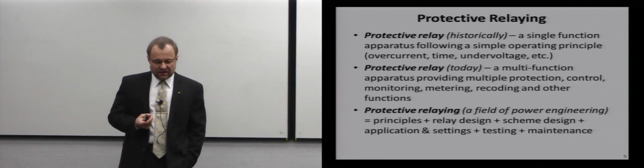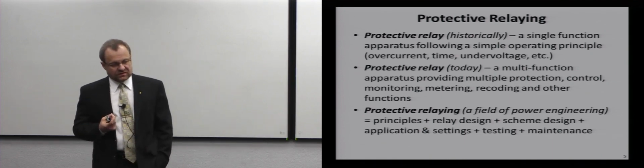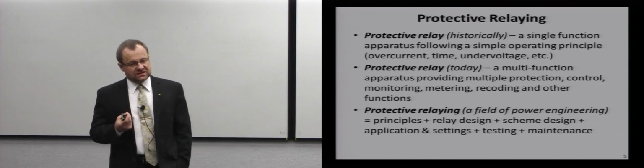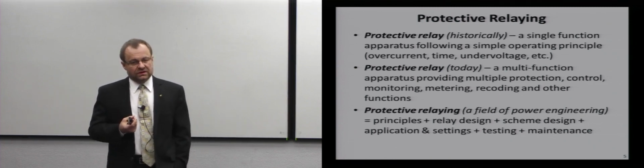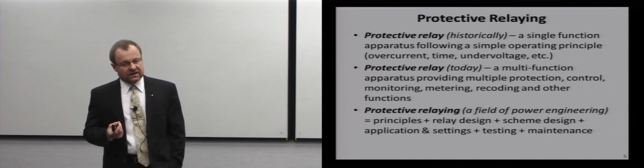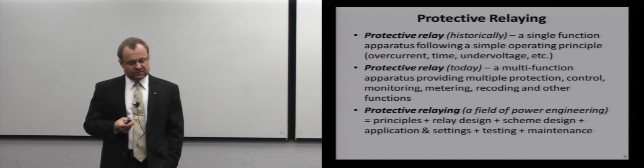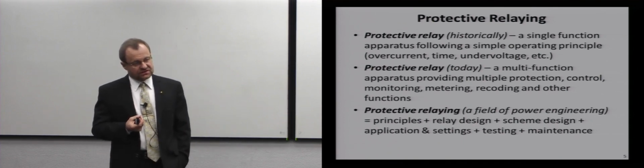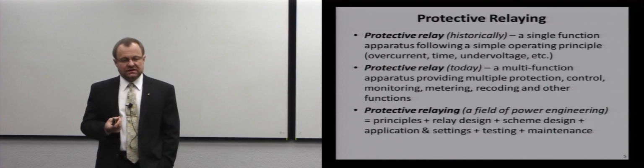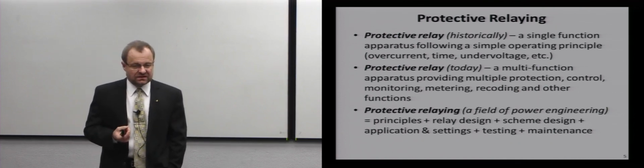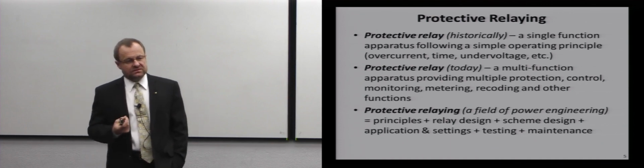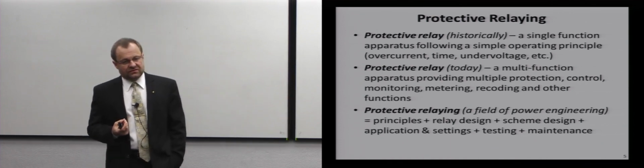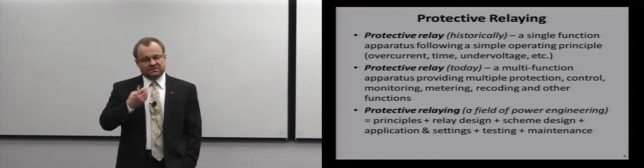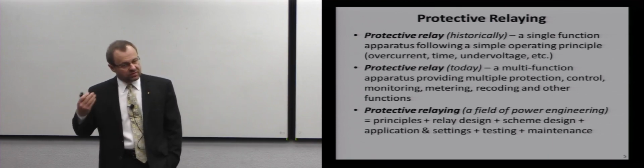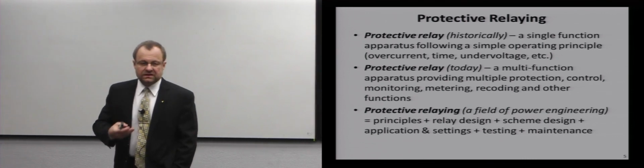Then you have application practitioners that put those devices together to build schemes, such as a full protection scheme for a transmission line or a big transformer. You have to be able to do settings, meaning configure those devices properly for a given installation. Then you have to test them, you have to maintain them. So there is a whole life cycle, so to speak, of the technology, when you have to know the protection principles, build an apparatus, build a scheme, deploy it in the field, set it correctly, maintain it.